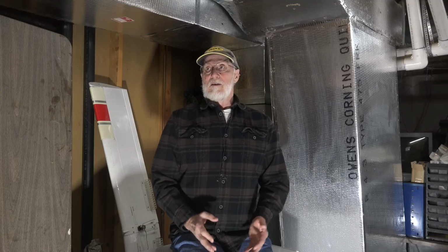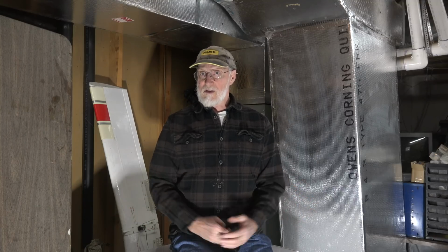There are some things that this video won't do. There's quite a bit of ductwork out there that really wasn't done very well to start with. And that's kind of unfortunate. However, it is one of the things that you should be looking for. Is there excessive drop in the return? Is there excessive drop in the supply? You can't fix something that has a problem with ductwork without considering the quality of the ductwork that's installed.